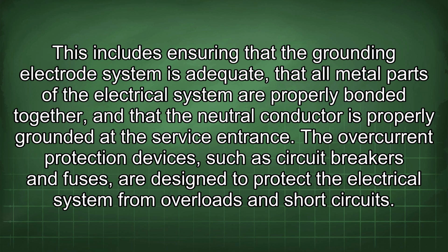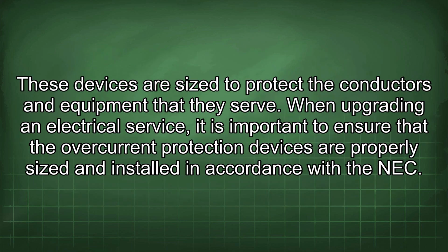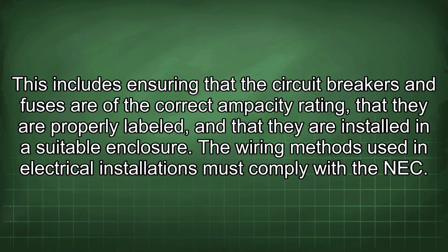The overcurrent protection devices, such as circuit breakers and fuses, are designed to protect the electrical system from overloads and short circuits. These devices are sized to protect the conductors and equipment that they serve. When upgrading an electrical service, it is important to ensure that the overcurrent protection devices are properly sized and installed in accordance with the NEC. This includes ensuring that the circuit breakers and fuses are of the correct ampacity rating, that they are properly labeled, and that they are installed in a suitable enclosure.